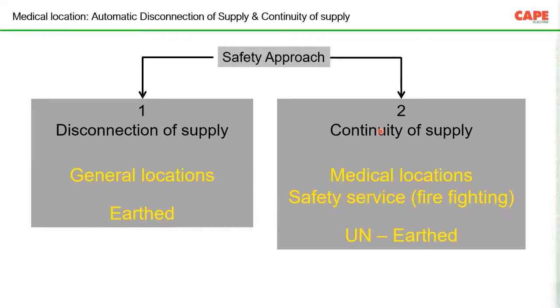So if disconnection happens in that kind of an area, the patient will be in danger because the supply itself has been disconnected. For that application, especially in group 2 medical locations, continuity of supply is important. What do we mean by continuity of supply? Continuity of supply means even if you use faulty equipment, or even if there is a first fault, the supply shall not disconnect. The supply shall continue.